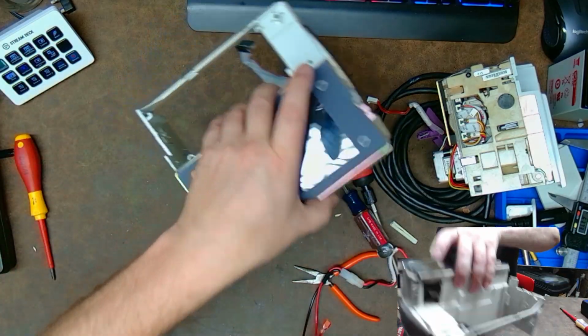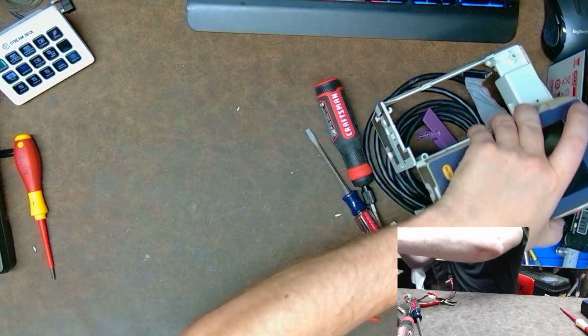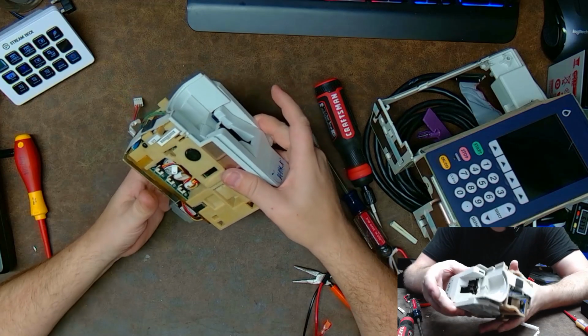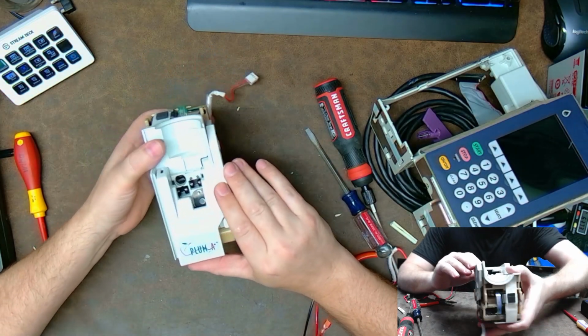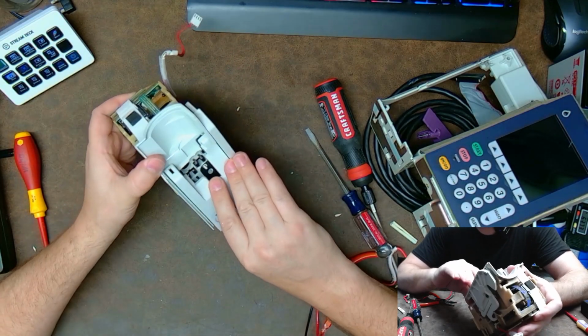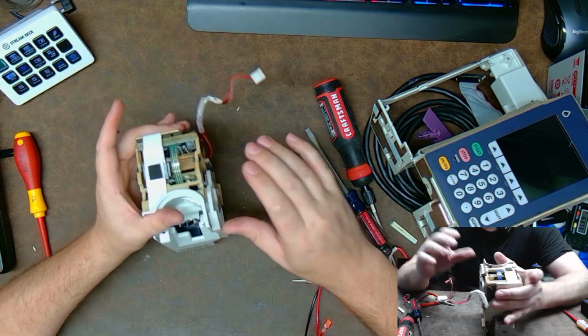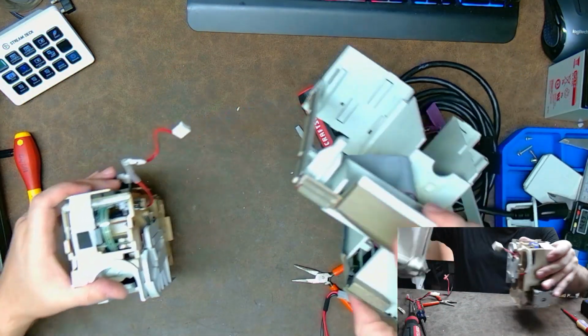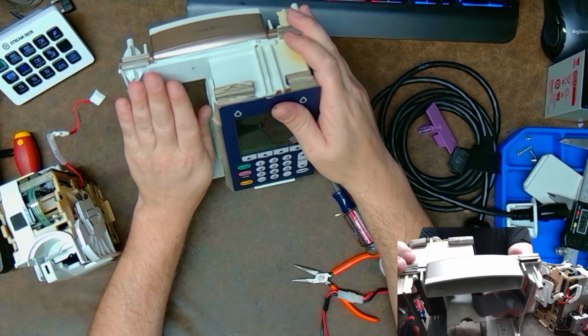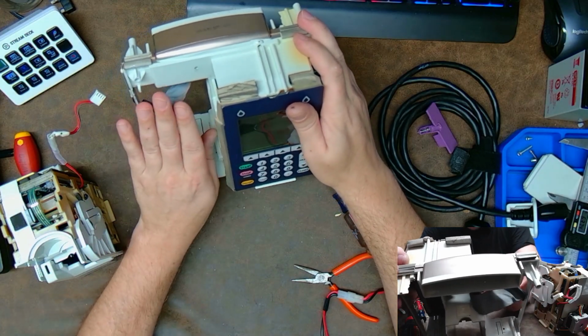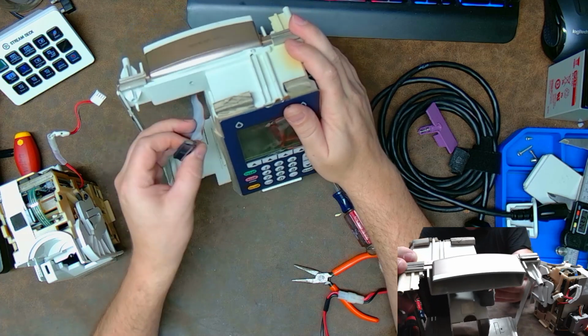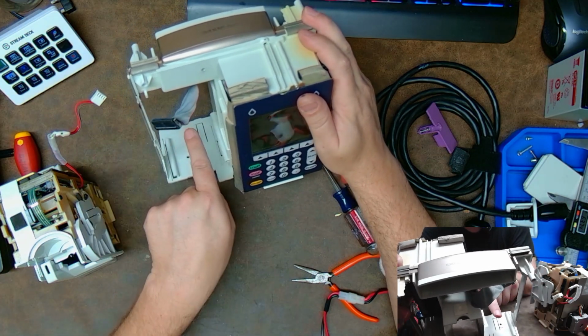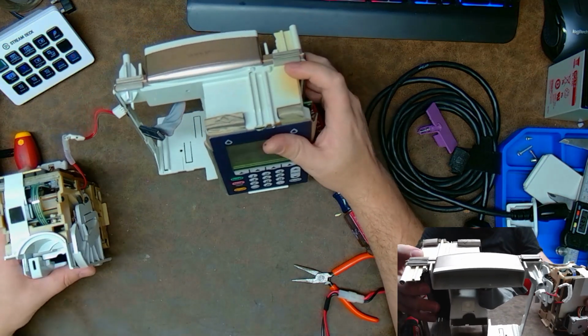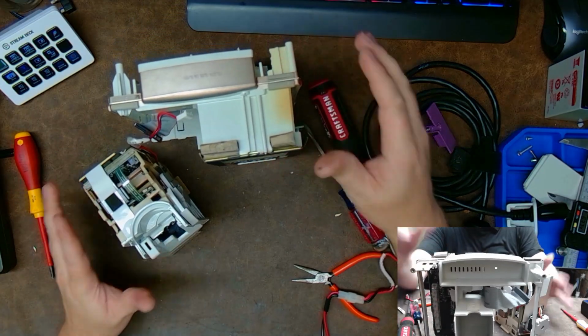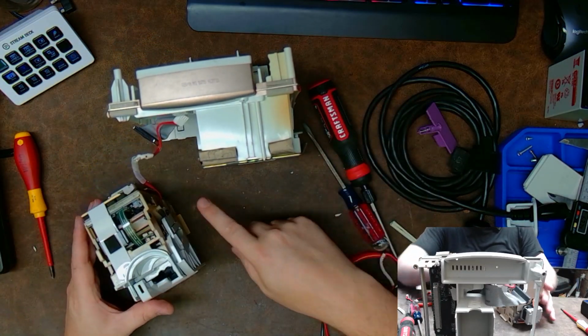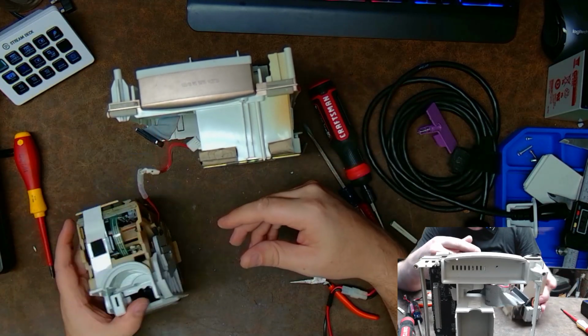All right, let's take a look at that pump module. So here's the interesting thing about these pump modules, is the company that manufactures these, they have a calibrator for this, right? And the way the calibrator works is instead of the pump sitting inside right here, there's actually a flat panel. I've seen video of it. And there's a ribbon cable, kind of like this guy right here, that connects to the front. And from there, it runs to external pumps so that you can calibrate them, kind of like this. You set them on your desktop, and externally, you plug that in, and you can calibrate your pumps.